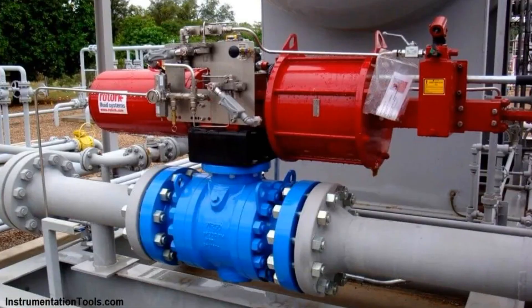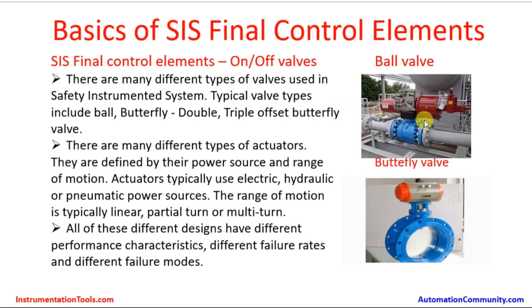Regarding on-off valves, there are many different types of valves used in the safety instrumented system. Typical valve types include ball valves, butterfly valves — including double and triple offset butterfly valves. Here we see two pictures: one is a ball valve fitted with an actuator connected to the process pipe, with a pneumatic assembly including solenoid valve, instrument air filter regulator, etc., mounted with a double-acting actuator. The bottom picture shows a butterfly valve with an actuator, where the disc moves against the pneumatic force.